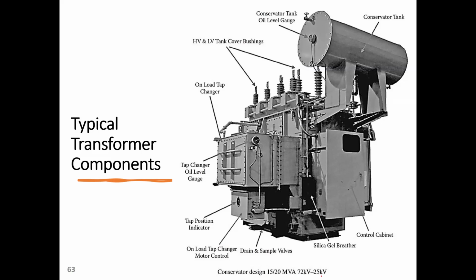If I have 72 and 25, how can I recognize which side is 72 and which side is 25? This can simply be figured out by the insulation and bushing of these transformers. Here, this bushing insulation is longer compared to that one. So the longest one is going to be the higher voltage. Okay, guys, so this is, for instance, how we can figure this out. But what are all the other parts of the transformer? I'm going to make a quick description of the other parts of the transformer here, just to let you know what we have in reality. So it's not just terminals and windings or core. We have a lot of other functions in our transformer.